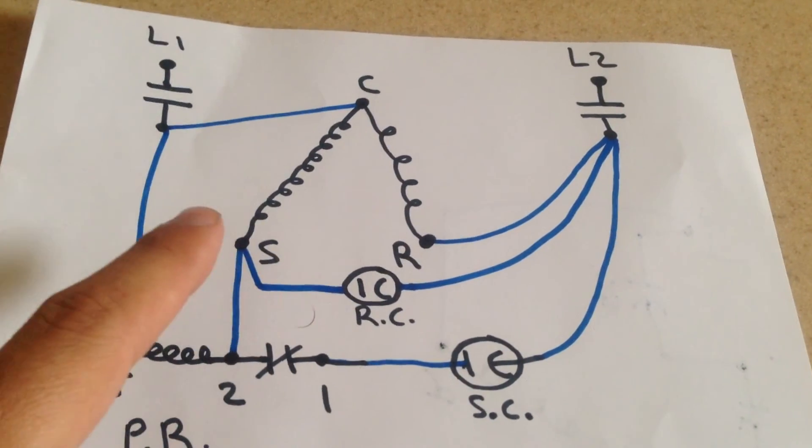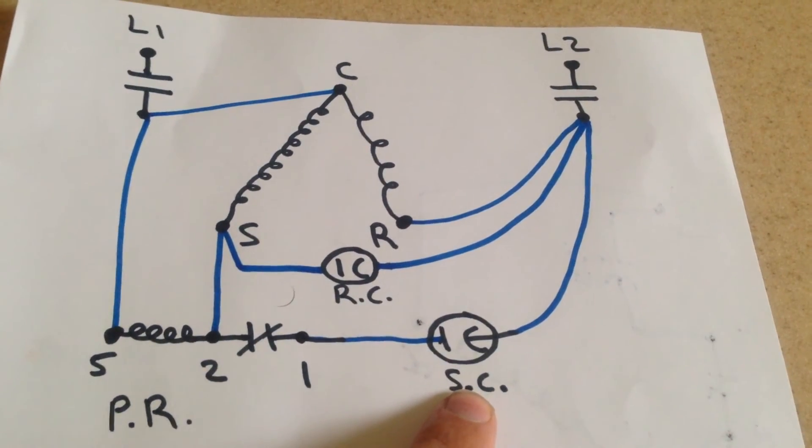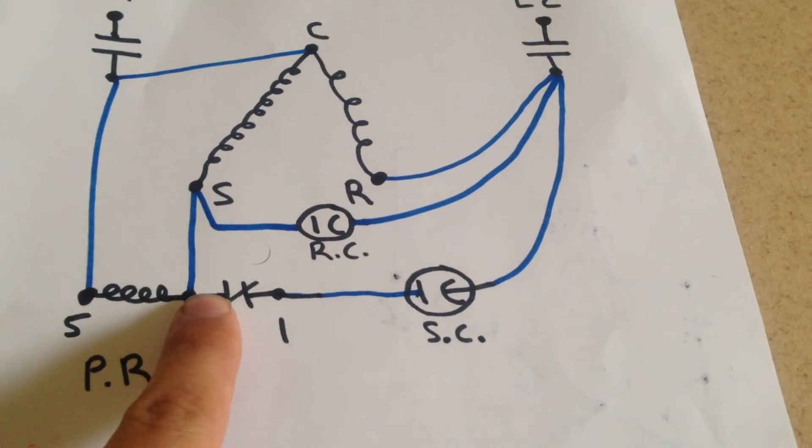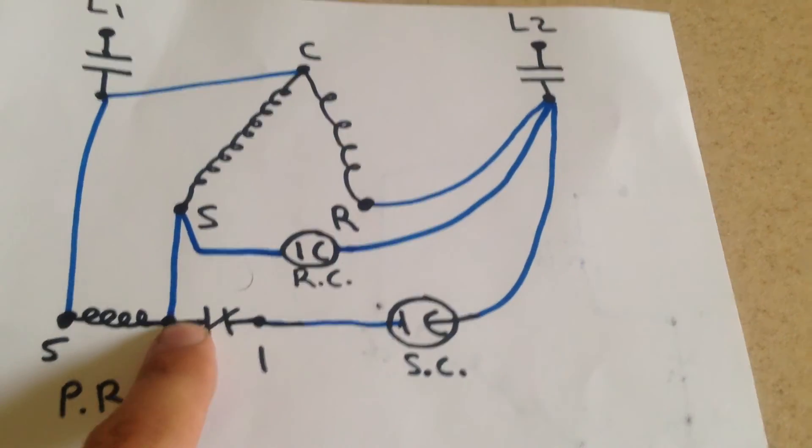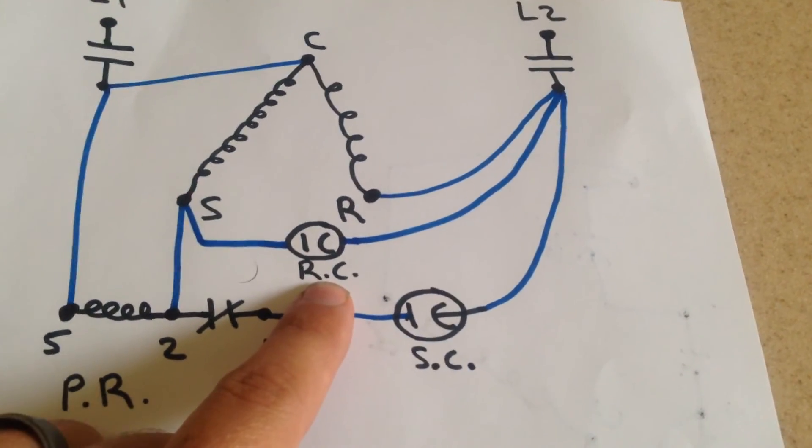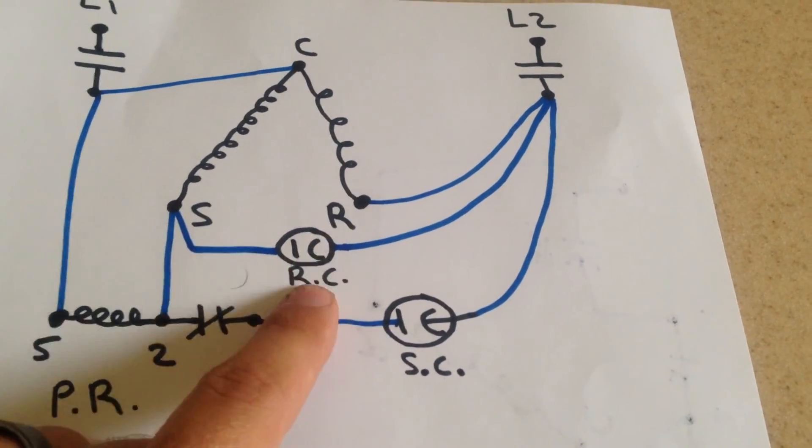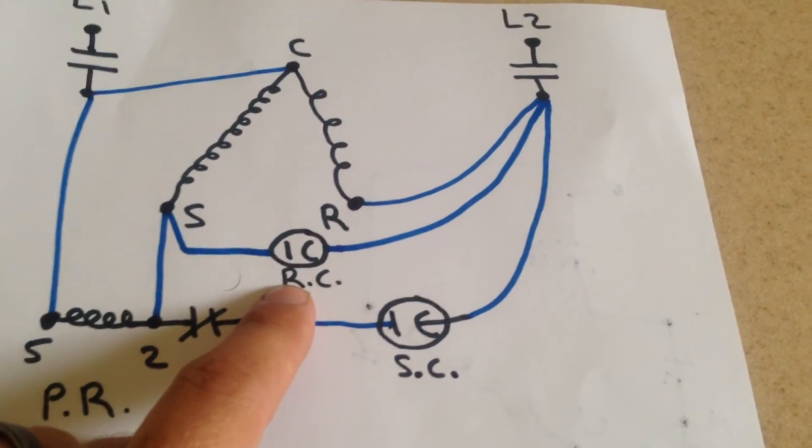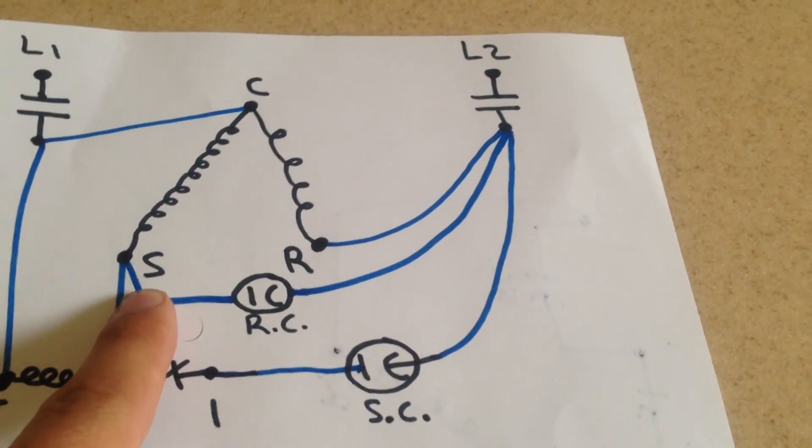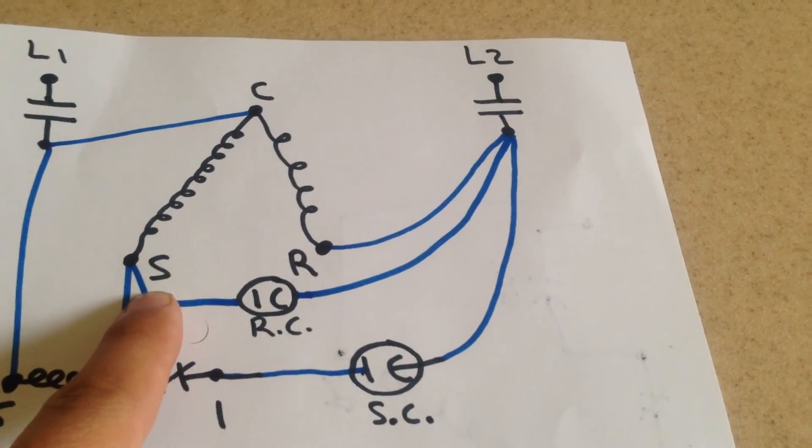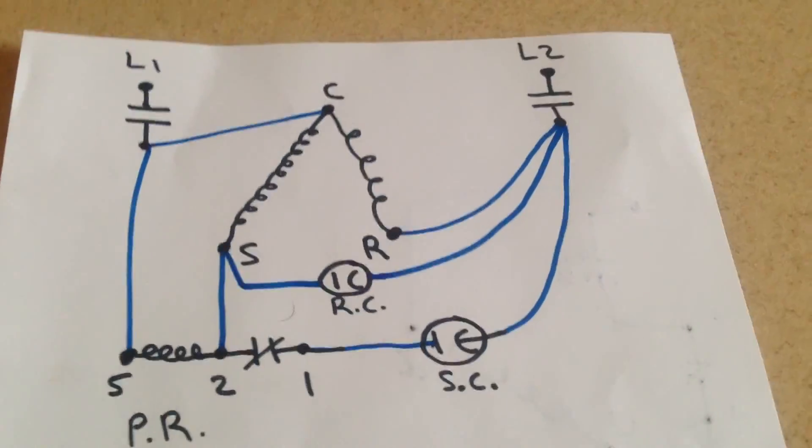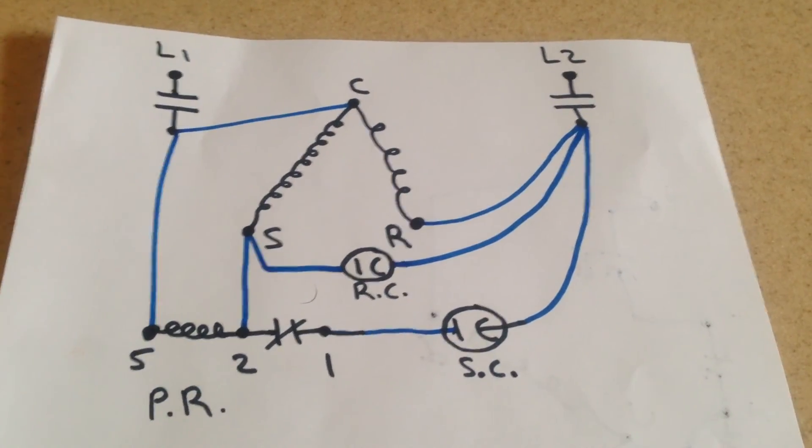And once the motor is up to speed, it's going to drop the start capacitor out of the circuit by opening this contact here. And then all we'll be left with in this application is our run capacitor continuing to assist the efficiency of our compressor in operation. So hopefully this helps you guys out and thank you for watching.